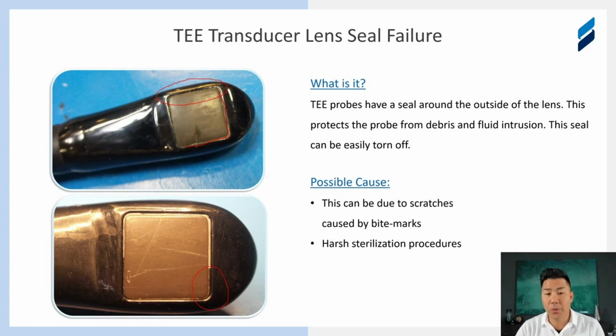And it's very repairable. We can seal that back up. But the major concern is not the seal itself failing. It's the opportunity for any fluid, whether it be stomach acid or sterilization fluid, getting inside the electronics, causing corrosion. Corrosion's a big deal in probes. Once something starts to corrode, you have a window of time to be able to catch that and make the repairs and clean it up.